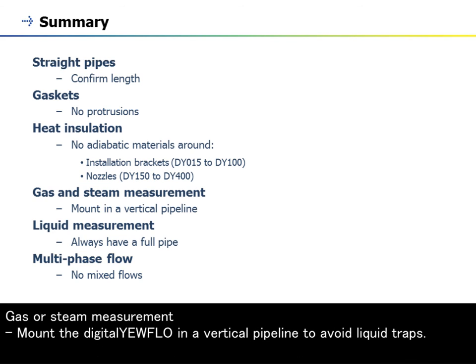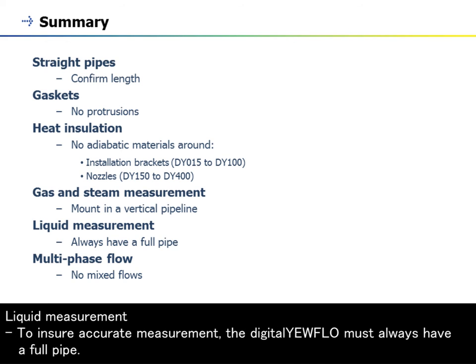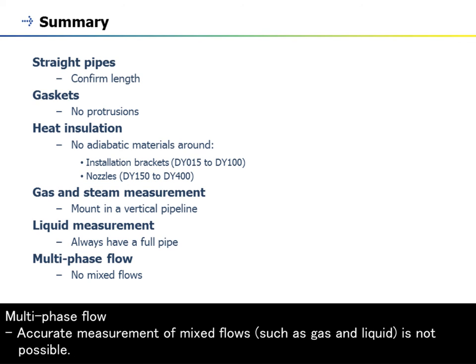Gas or steam measurement: mount the digitalYEWFLO in a vertical pipeline to avoid liquid traps. Liquid measurement: to ensure accurate measurement, the digitalYEWFLO must always have a full pipe. Multi-phase flow: accurate measurement of mixed flows, such as gas and liquid, is not possible.